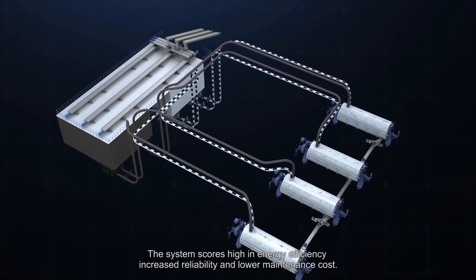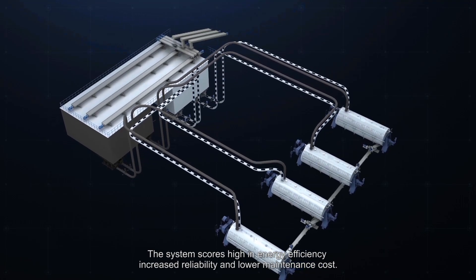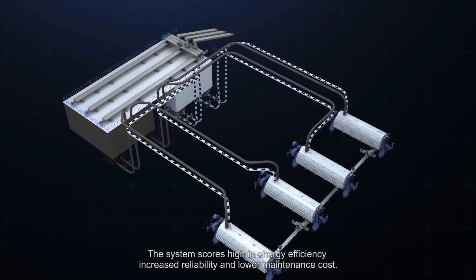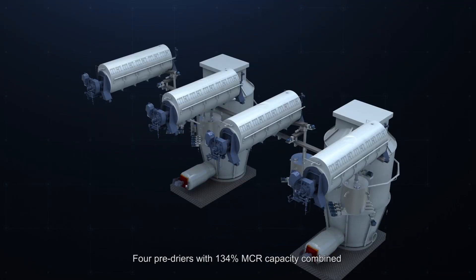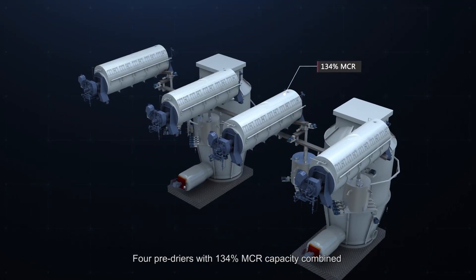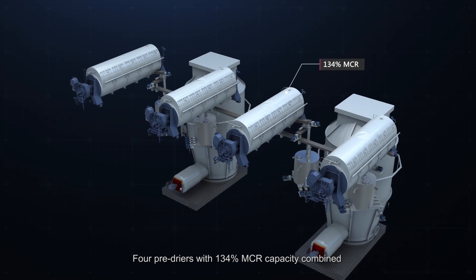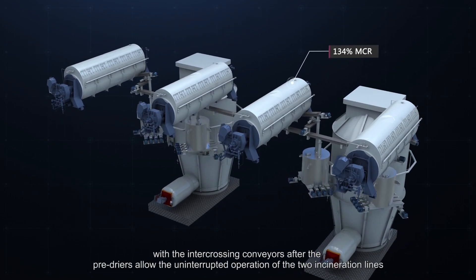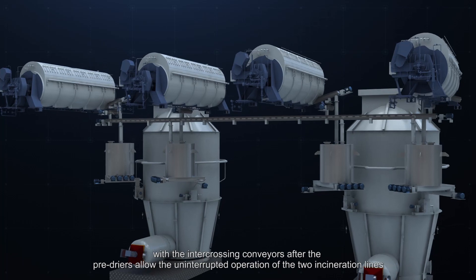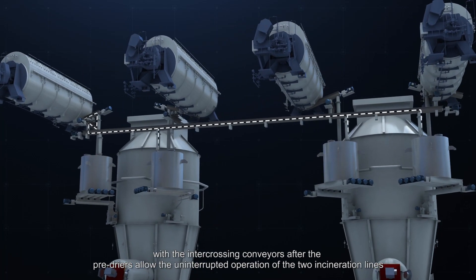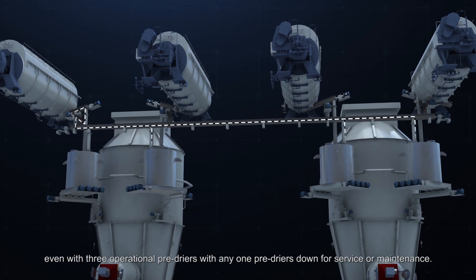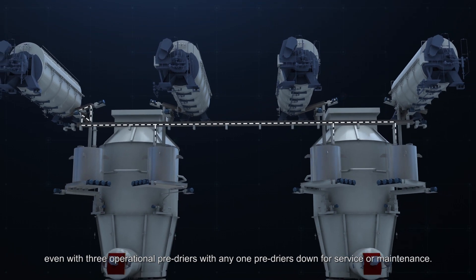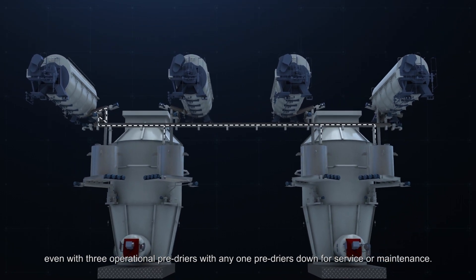The system scores high in energy efficiency, increased reliability and lower maintenance cost. Four pre-dryers with 134% MCR capacity combined with the inter-crossing conveyors after the pre-dryers, allow the uninterrupted operation of the two incineration lines, even with three operational pre-dryers with any one pre-dryers down for service or maintenance.